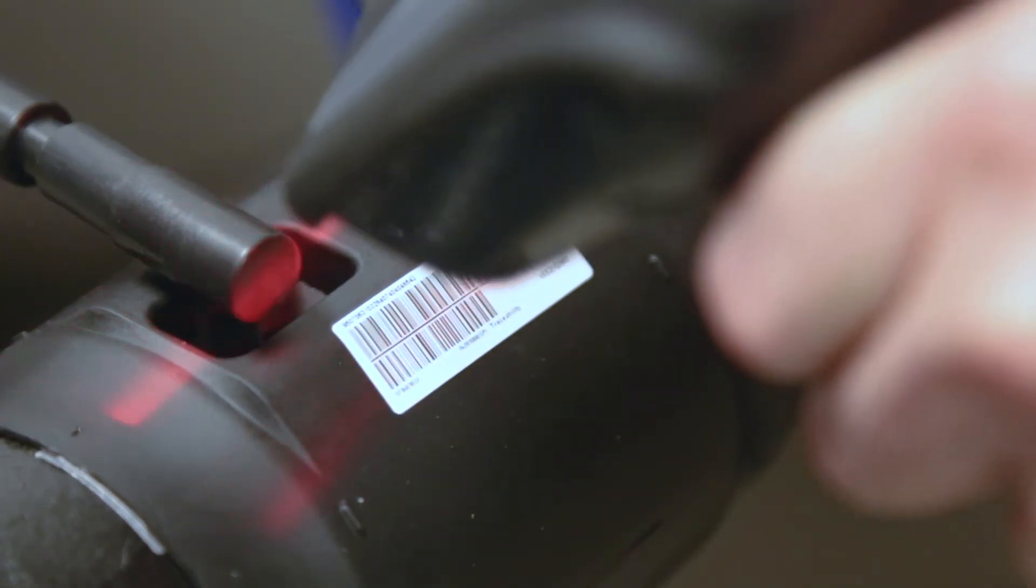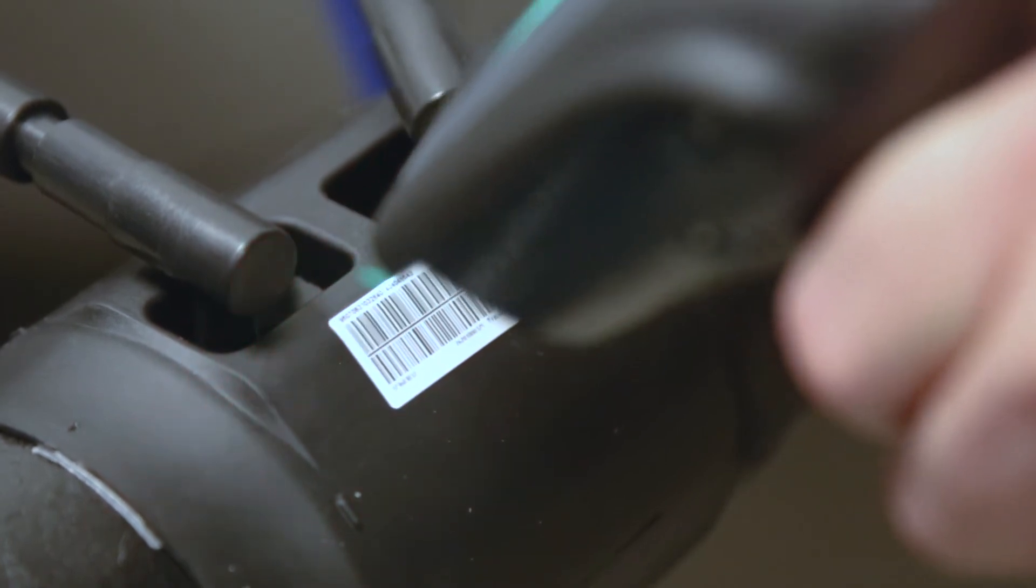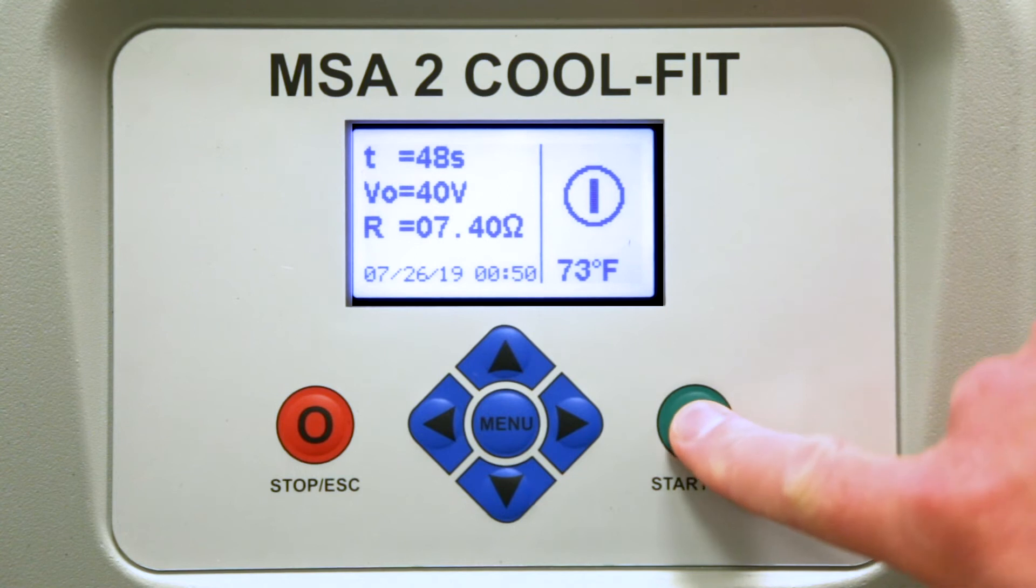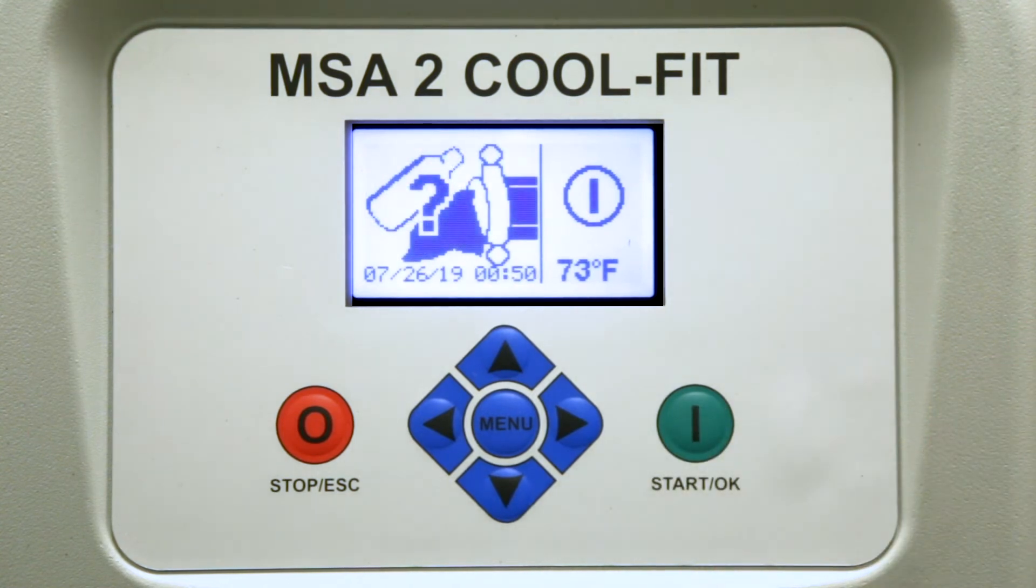Use a scanner to read the barcode to input the welding parameters. Press the green button on the welding machine and follow the fusion steps as shown on the screen. Confirm you've peeled and cleaned the pipe.